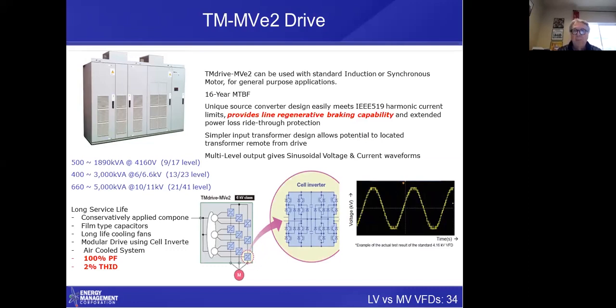We had a wind tunnel once where the motor was suspended in the middle of the wind tunnel, and we had a drive quote, but every pound was important. We talked to the motor manufacturer and said, is there any way that you can reduce the weight of this motor? Well, that's kind of tough, but they said, show us your output voltage waveform on the drive. We showed them this waveform, and they said, oh man, that's like a sine wave. I think this was a 3,000 horsepower motor, and they took 2,000 pounds out of that motor, all insulation, because of the output waveform.